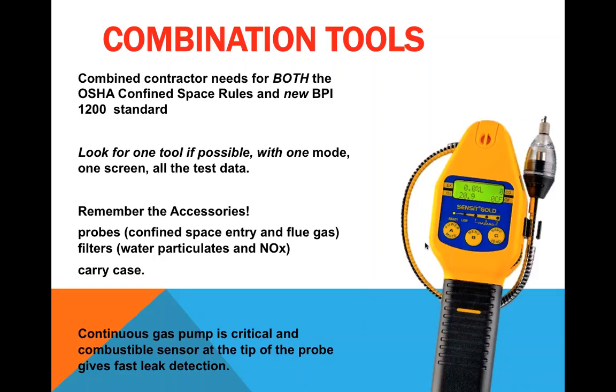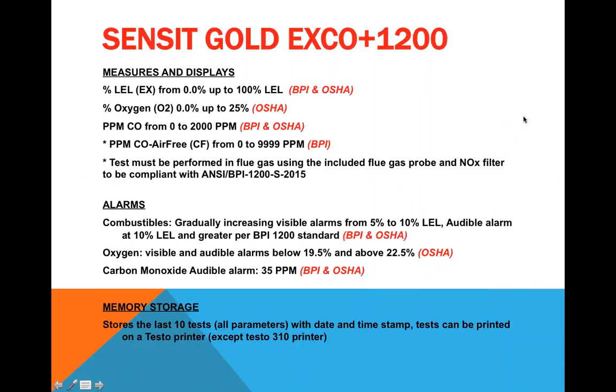So we put this whole product kit together with a continuous pump. It's also got the gas leak sensor at the tip of the probe that gives fast reaction. The combustion sensors are buried inside the device, but if you're looking for a quick leak detector, it's done right here at the tip of the probe. So this is sort of a sales pitch, but it's what you want to look for. If you can get a tool that does multiple things, you're usually further ahead.